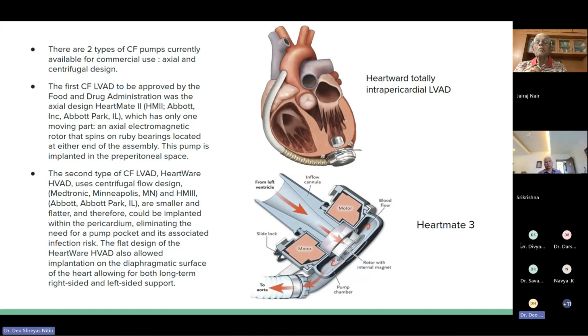The second type of continuous flow LVAD uses centrifugal flow design. The HeartWare by Medtronic and HeartMate 3 by Abbott are smaller and flatter and therefore could be implanted within the pericardium, eliminating the need for a pump pocket and its associated infection risk. The flat design of the HeartWare also allowed implantation on the diaphragmatic surface of the heart, allowing for both long-term right-sided and left-sided support. Here we can see the HeartWare totally intrapericardial LVAD and HeartMate 3.